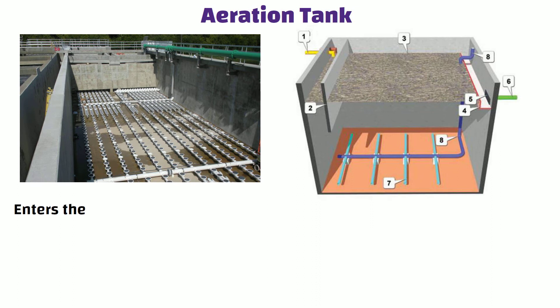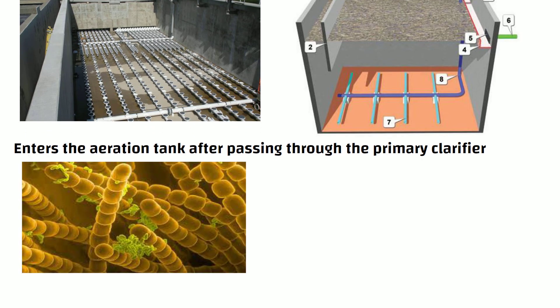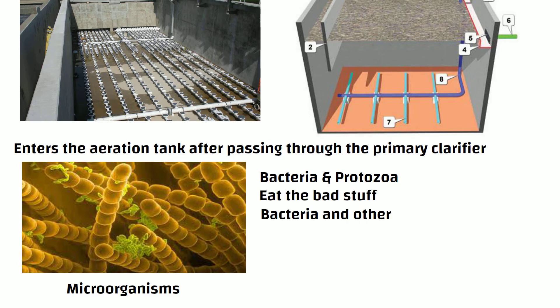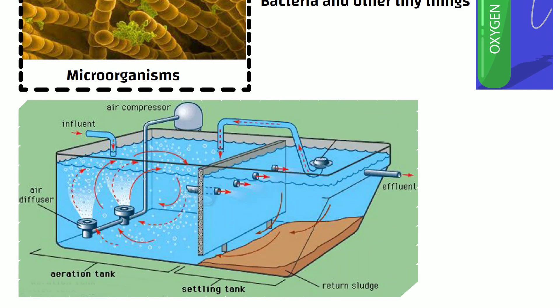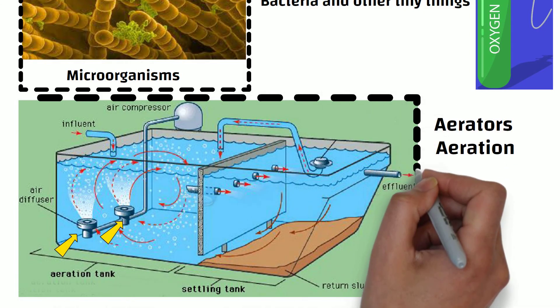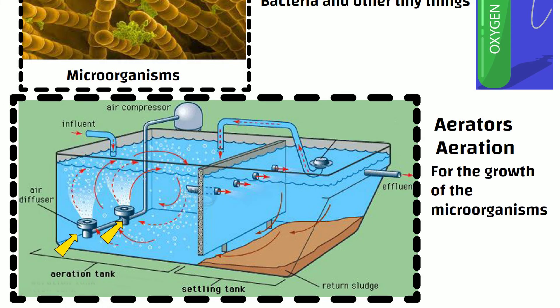Aeration Tank: the waste water enters the aeration tank after passing through the primary clarifier. The aeration process begins with the introduction of microorganisms such as bacteria and protozoa into the waste water. These microorganisms break down organic matter and other harmful substances in the water. In order for these microorganisms to survive, they need oxygen, which is added by blowing air into the water using machines called aerators — this process is called aeration. The process is carefully monitored for parameters such as dissolved oxygen, pH and temperature.